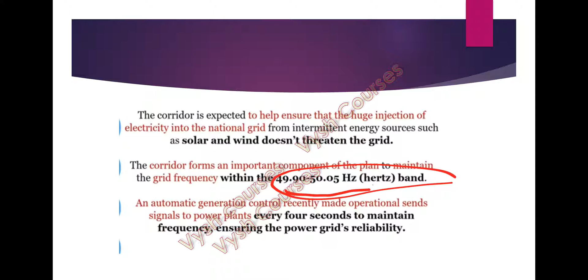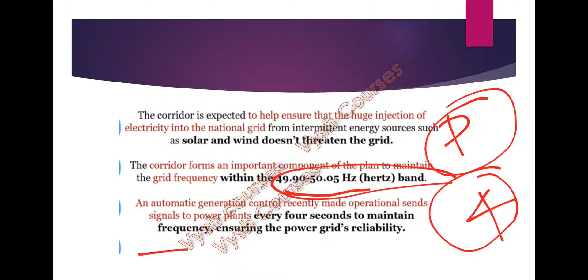In order to maintain the grid frequency, the frequency range is kept between 49.90 to 50.05 hertz. The automatic generation control, recently made operational, sends a signal to the power plants every 4 seconds to maintain this frequency and ensure the power grid's reliability.